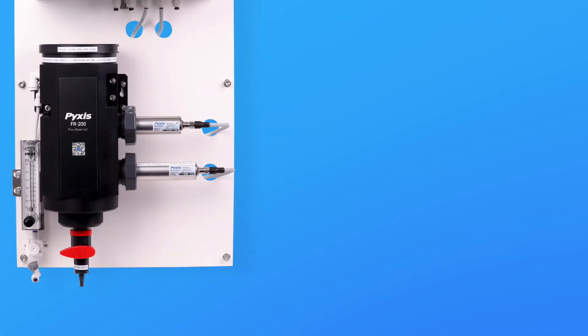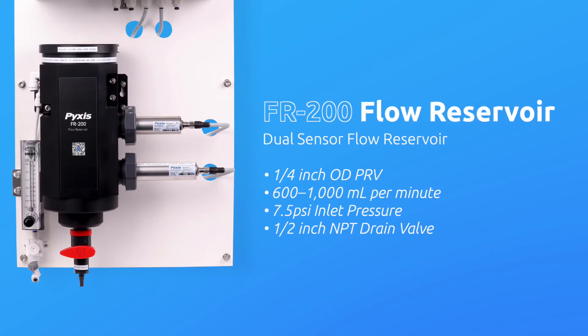The DW2100P panels incorporate Pyxis' uniquely designed FR200 dual sensor flow reservoir. The pre-mounted FR200 provides sample calming for dissipation of air bubbles and settling of suspended solids, foam, or other impurities commonly observed in drinking water influent. The panel is equipped with a quarter-inch OD inline pressure reduction valve and rotameter upstream of the FR200 for accurate flow and pressure regulation at the recommended flow range of 600 to 1,000 mL per minute. This proprietary flow reservoir design results in the highest level of turbidity resolution on the market and greatly extends the maintenance cycle of the sensors while providing buffering capacity to mitigate sample pressure fluctuations.